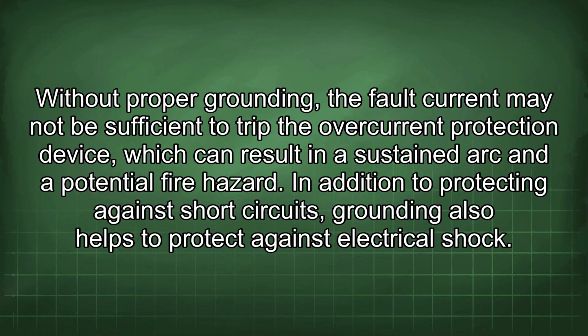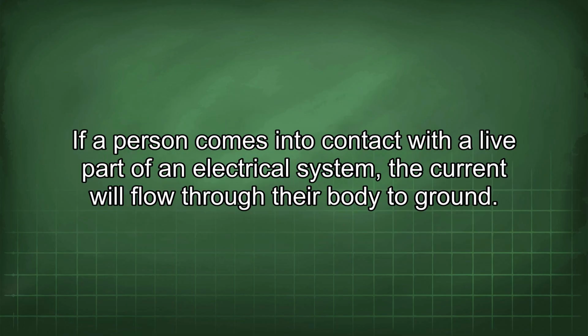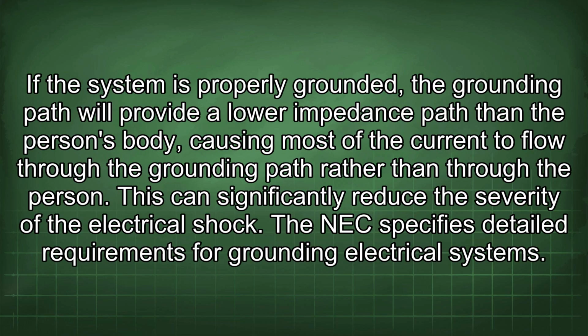In addition to protecting against short circuits, grounding also helps to protect against electrical shock. If a person comes into contact with a live part of an electrical system, the current will flow through their body to ground. If the system is properly grounded, the grounding path will provide a lower impedance path than the person's body, causing most of the current to flow through the grounding path rather than through the person. This can significantly reduce the severity of the electrical shock. The NEC specifies detailed requirements for grounding electrical systems.